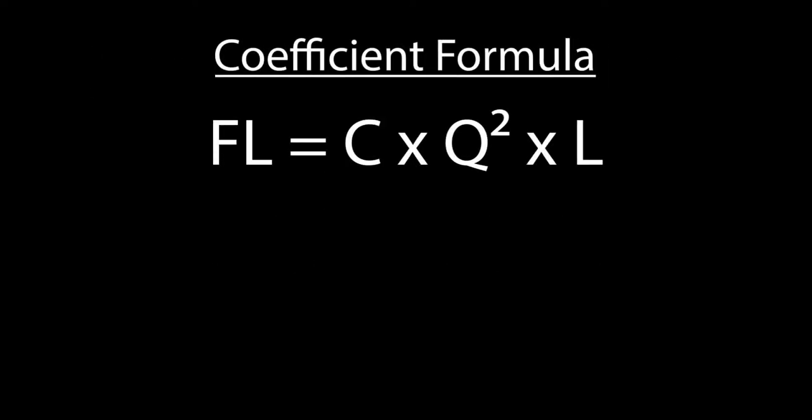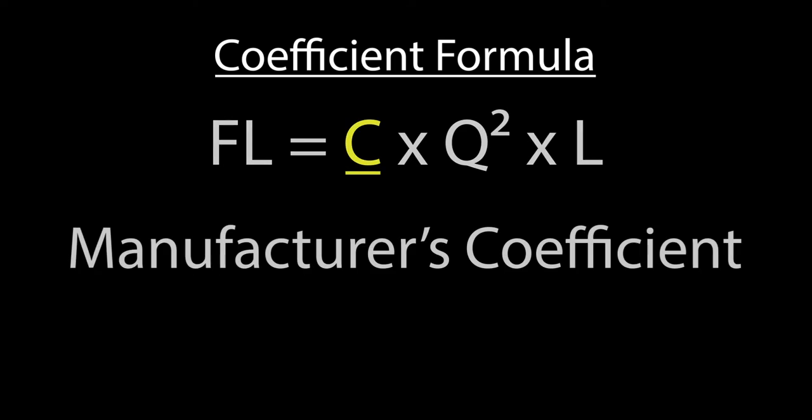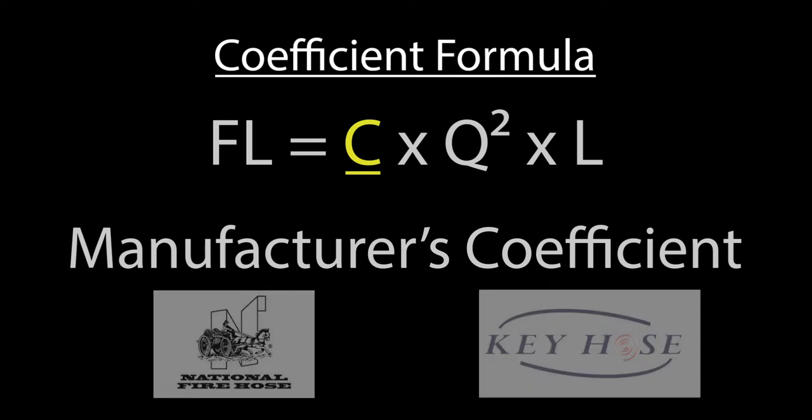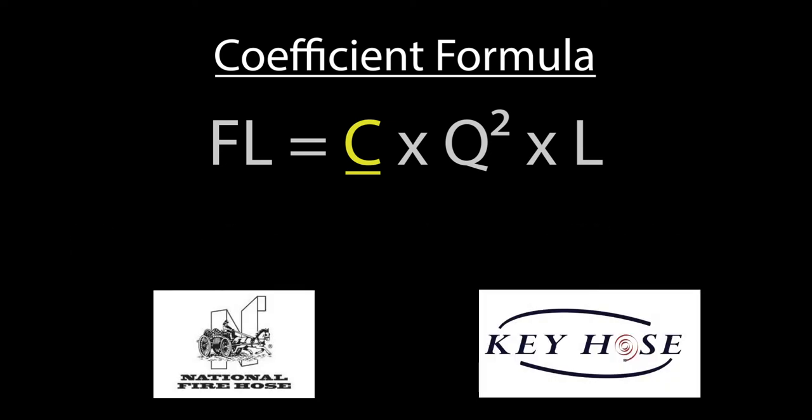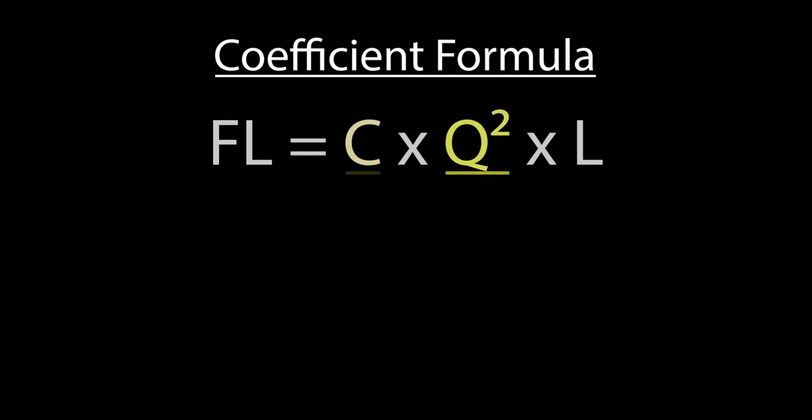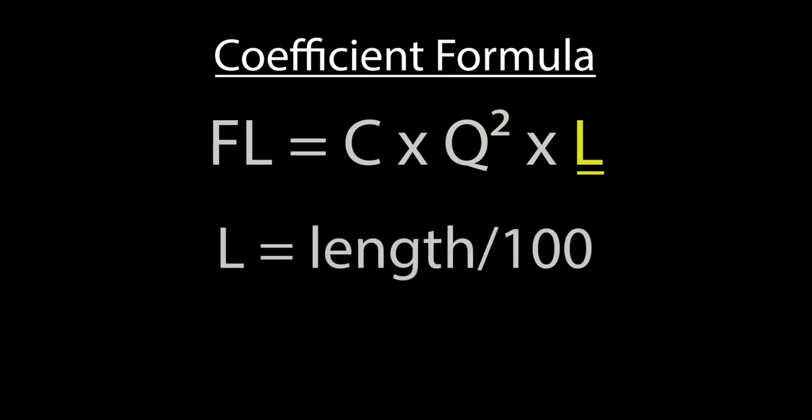To obtain the theoretical friction loss based on the coefficient formula, begin with the friction loss coefficient. Keep in mind that this number does vary between manufacturers and models of hose. Multiply by Q squared—Q is our GPM divided by 100. Finally, multiply that by L, which is the length of hose divided by 100.